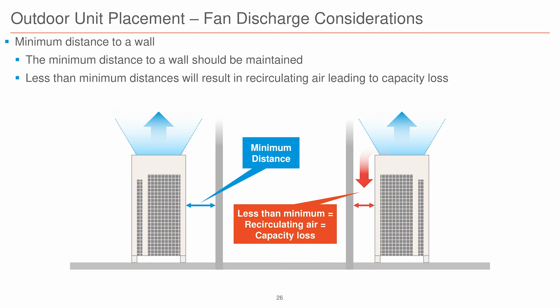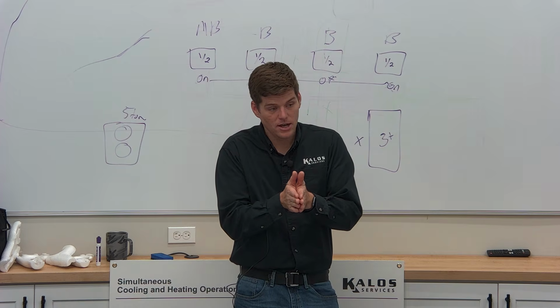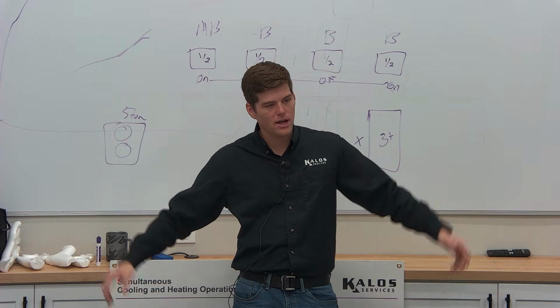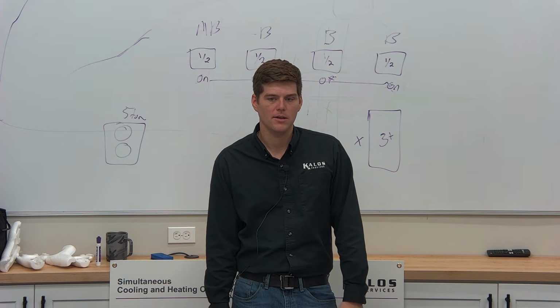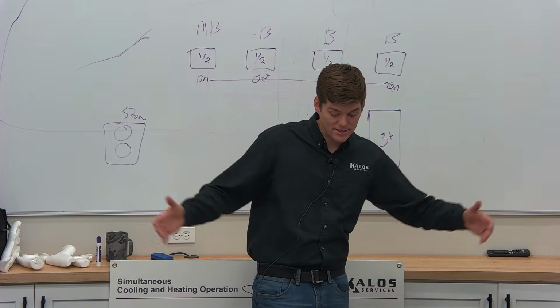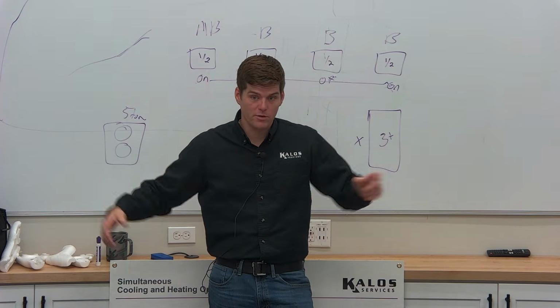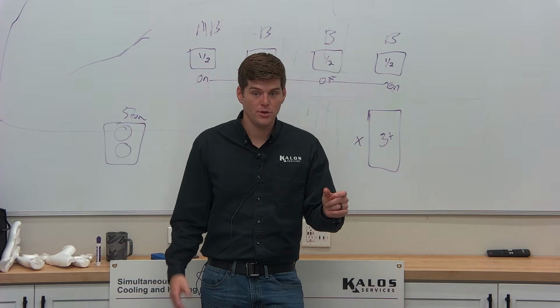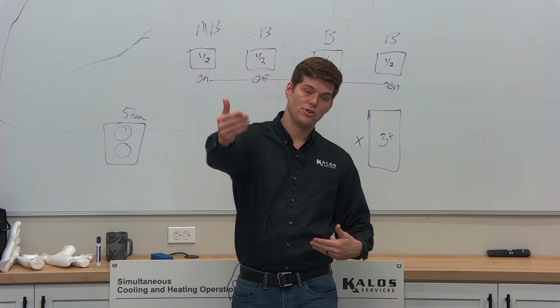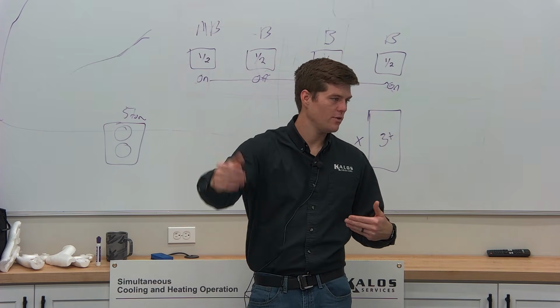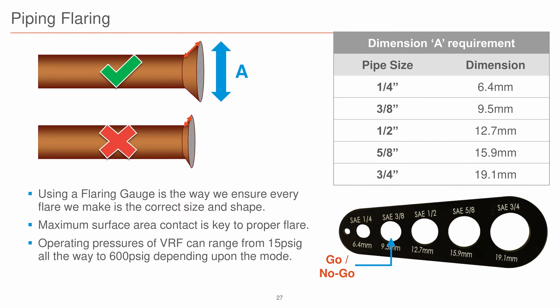We want to have enough room to where I actually can get rid of the hot air coming out of the unit, or the cold air coming out of the unit, so that we don't get that recirculation. You'll find in the installation manual what those minimum distances are. You're actually allowed to put the units up to 3/4 inches away from each other, side by side. It's the front, back, and other sides that become the issue of where the air is going to be coming in. So you can stack them three all together, sandwiched together with a 3/4 inch clearance. But when you do that, you have to make sure you maintain that 3 foot, 4 foot, 6 foot on the outside. Flaring, this is a good one.